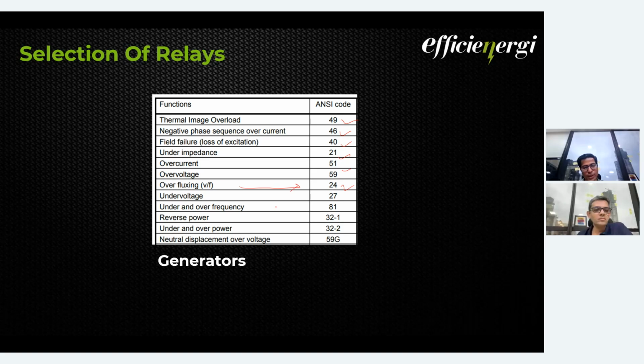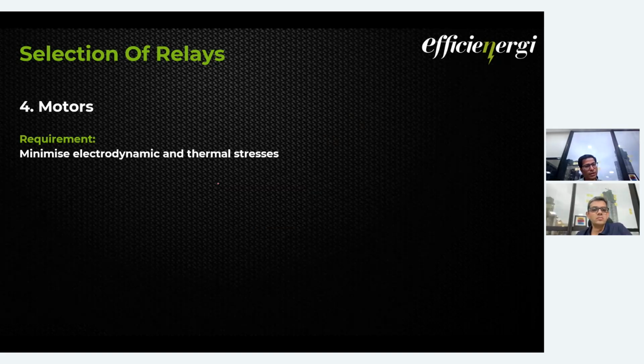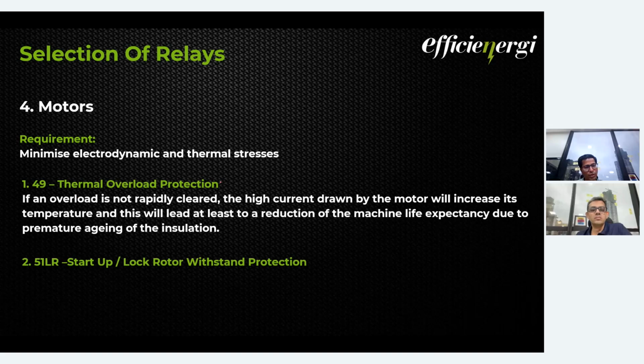Overfluxing, if we are using here, you can see neutral displacement 59G also we are using in bigger turbo generators. Field failure also we have to go for. Motors have the same requirements. Thermal overload protections, as you asked for, for motors we are considering 49. Then we are considering 51LR, that is for locked rotor and startup.